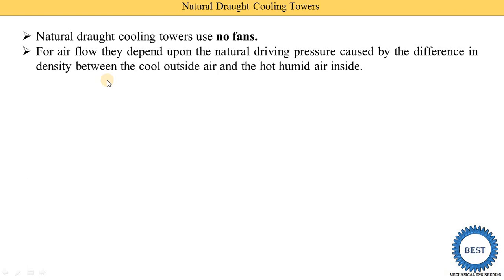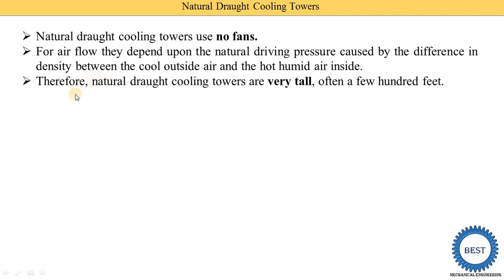Inside the cooling tower, hot humid air has low density and tends to move upward, while outside cool air has higher density. Due to this density difference, air circulation takes place. Therefore, natural draft cooling towers are very tall — a few hundred feet — compared to mechanical type cooling towers such as induced draft and forced draft cooling towers, because air circulation takes place naturally and requires a larger height.